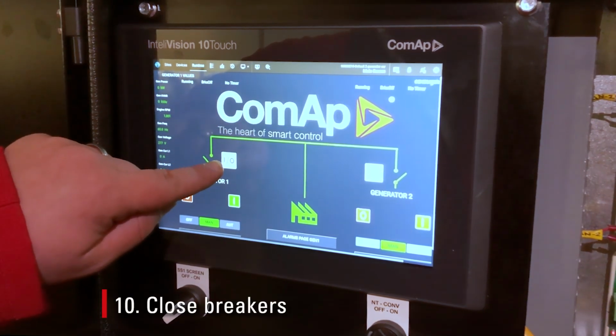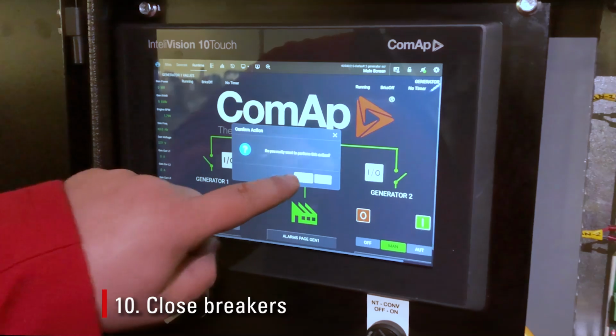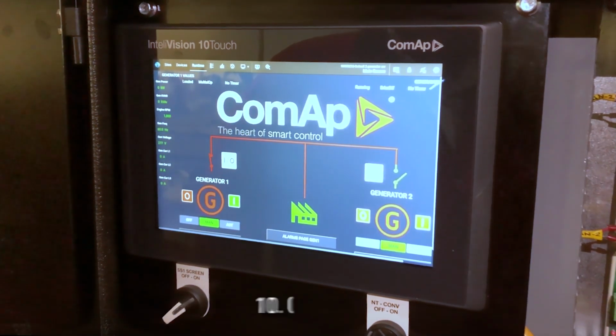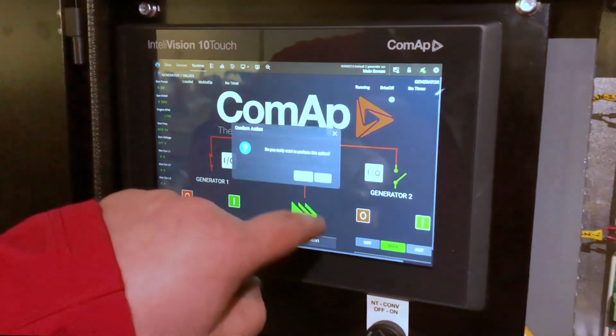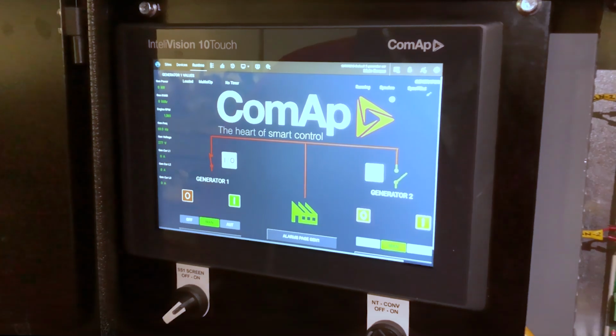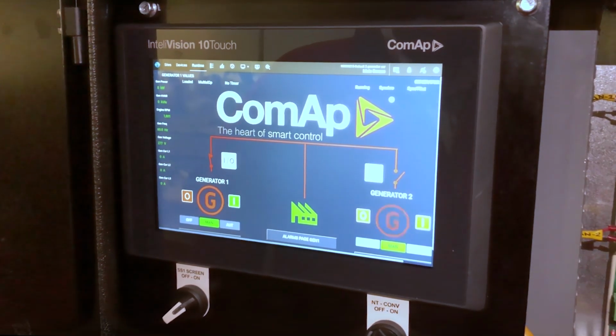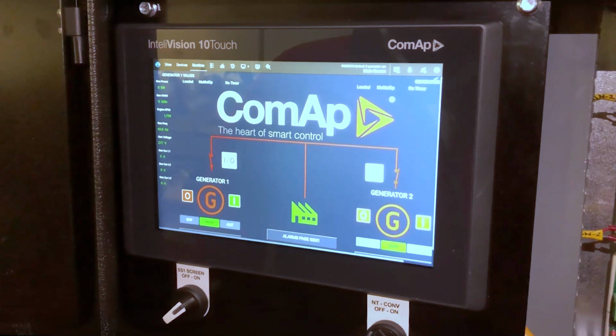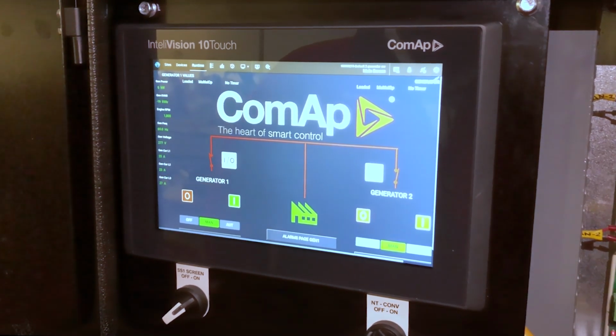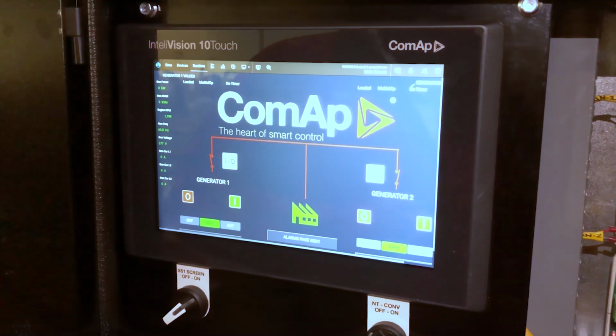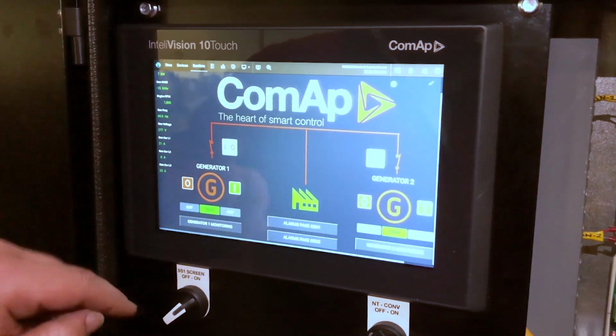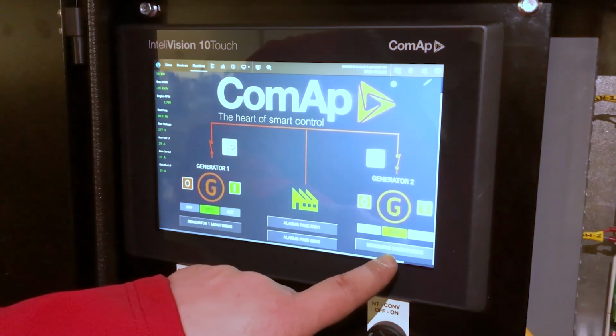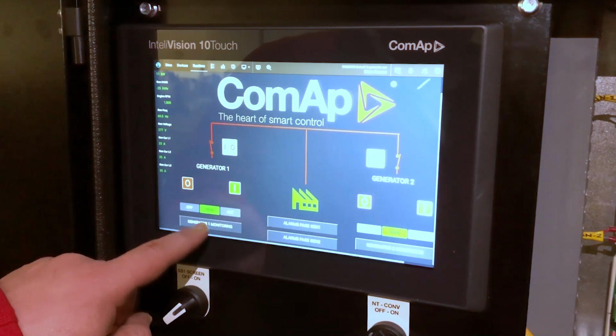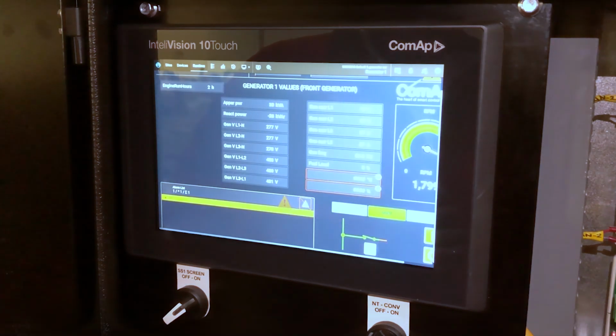The next step is to close each breaker through the display. Again, please note this is only necessary in manual mode. Once generator 1's breaker is closed, the indication will show it's on the bus. We can now close generator 2's breaker. Please note it will take a few seconds to synchronize to the bus. Now we can see both gensets are connected to the bus. To see detailed information regarding the operation of the gensets, you can navigate the screen down to the generator monitoring buttons. Here I am clicking on the generator 1 monitoring button, and now I can see the live information regarding operation.